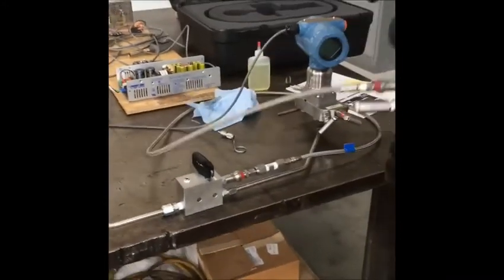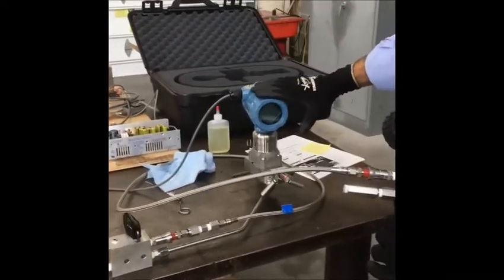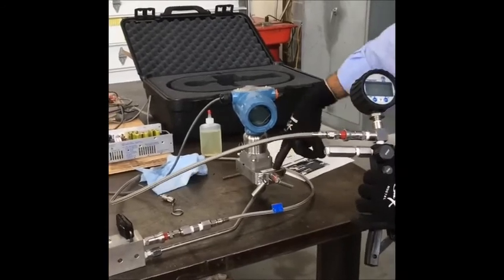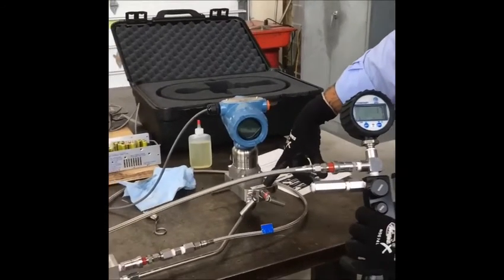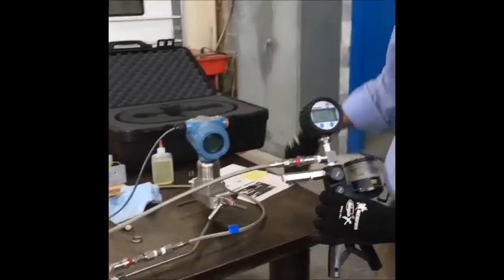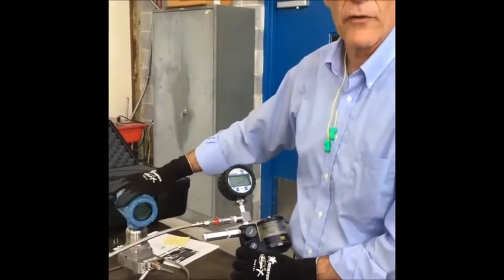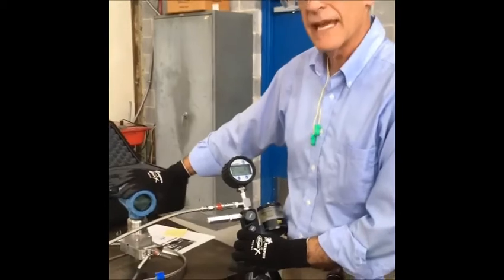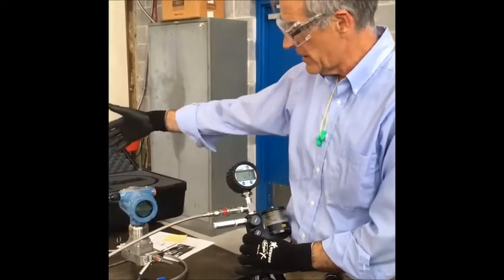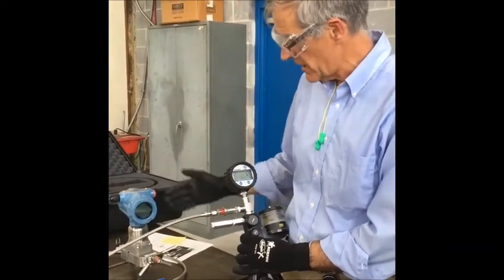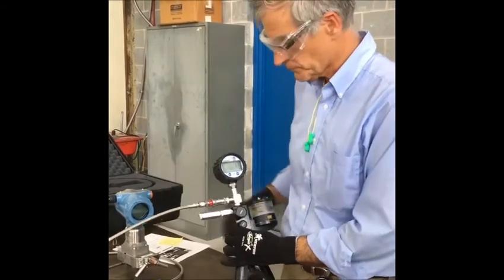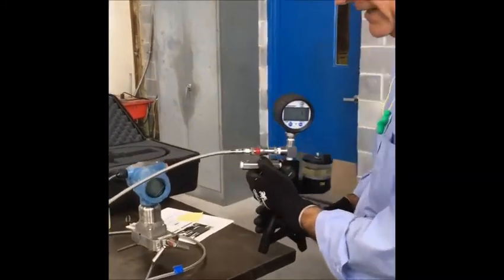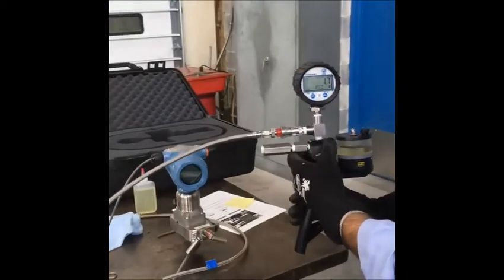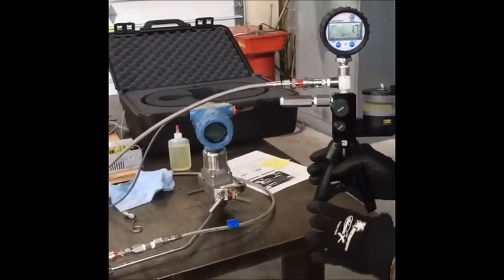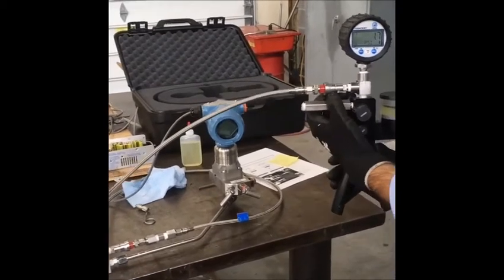So now in our test setup today, we have a Rosemount pressure sensor that is simulating our high pressure cutout. On a real compressor system, this would be your high pressure cutout, or the transducer that's probably indicating discharge pressure and wired into control panel. It would cut out the machine as you come up to pressure. So we will be creating that pressure with oil pressure now to bring us up to the point that will cut off the compressor as we test the high pressure cutout.